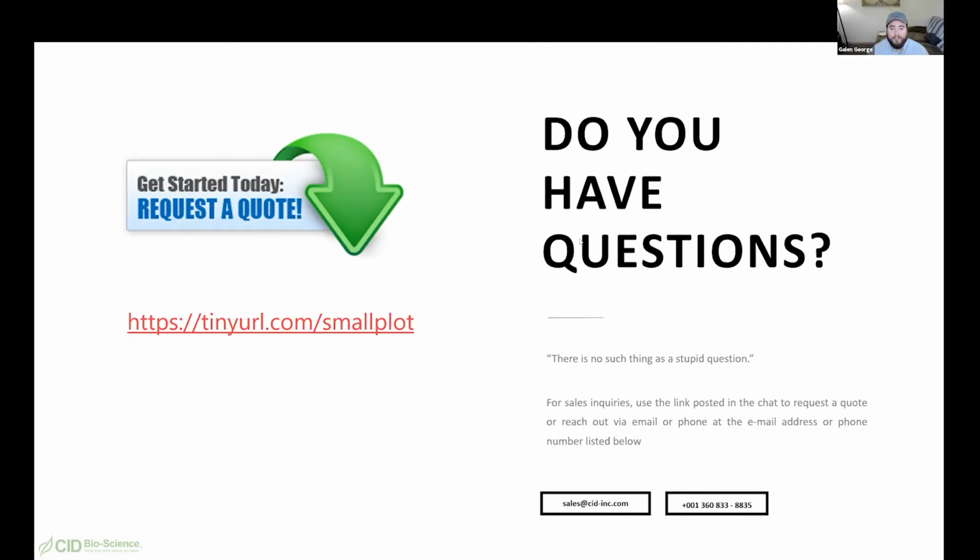Awesome. Looks like we got one more question in here actually while we were answering that one. And that's just a question about the CI 602 versus the CI 600. Is the CI 602 more advanced than the CI 600? And in some ways, yes, it is. The fact that it does go up to 1200 DPI resolution, whereas the CI 600 is limited to 600 DPI resolution. The CI 602 is also a smaller diameter, and so that might help more applications. It also fits into BART's tubes. So if you already have tubes from the BART system installed, you can easily use the CI 602 that fits inside those tubes. And so those are the two major differences between the two models.